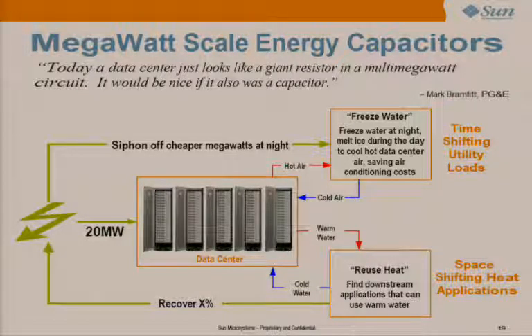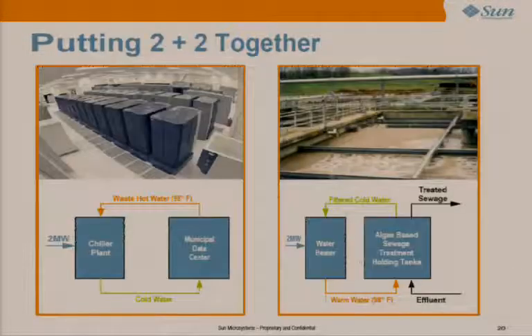So you're shifting the energy cost not just in time, but you can also shift it in space. How can you do that? Well, it turns out that the exhaust heat that comes out of a data center is pretty low-grade heat. It's water that comes out of the chillers that service the air conditioner at maybe 98 to 100 degrees Fahrenheit. It's not hot enough to boil water or drive a steam turbine or regenerate electricity through any kind of cogeneration activity. But you can find applications downstream that could make use of the warm water.